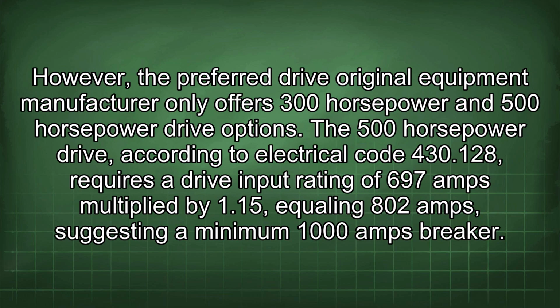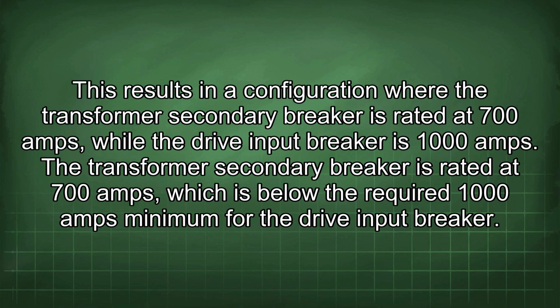However, the preferred drive original equipment manufacturer only offers 300 horsepower and 500 horsepower drive options. The 500 horsepower drive, according to Electrical Code 430.128, requires a drive input rating of 697 amps multiplied by 1.15, equaling 802 amps, suggesting a minimum 1000 amps breaker. This results in a configuration where the transformer secondary breaker is rated at 700 amps, while the drive input breaker is 1000 amps. The transformer secondary breaker is rated at 700 amps, which is below the required 1000 amps minimum for the drive input breaker.